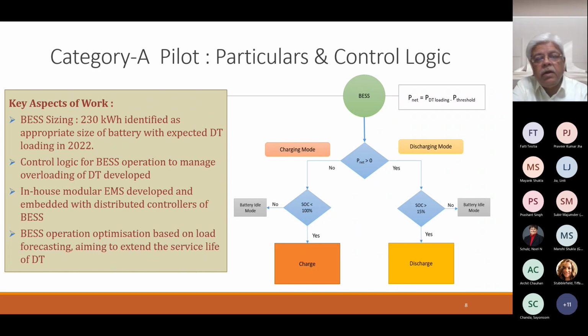Let's say we take it as 100 to 1000 kVA DT, then 80% of DT loading becomes 800 kVA. So whenever the DT loading becomes more than that 80% threshold level, the DT becomes overloaded, and at that point we have to discharge the batteries or supply power through the battery energy storage systems.